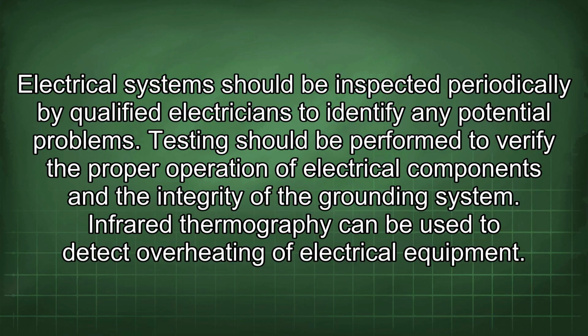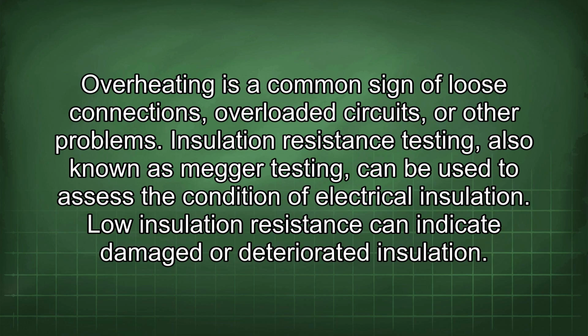Infrared thermography can be used to detect overheating of electrical equipment. Overheating is a common sign of loose connections, overloaded circuits, or other problems.